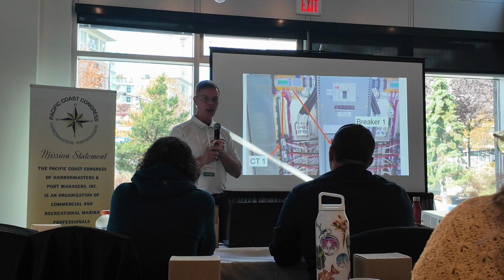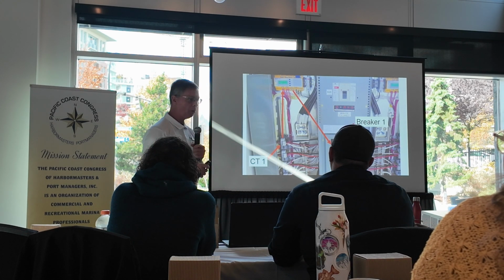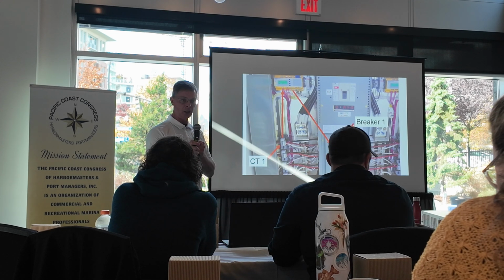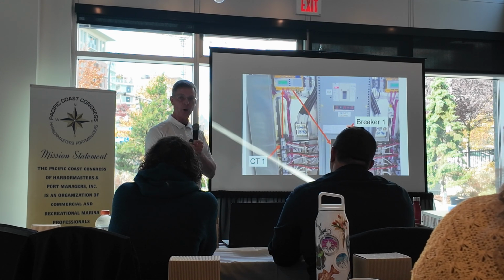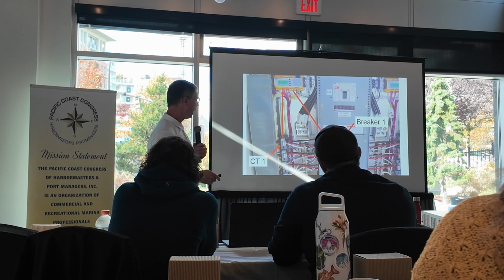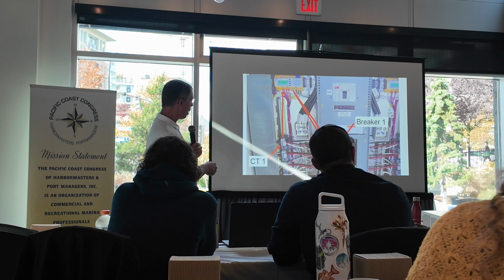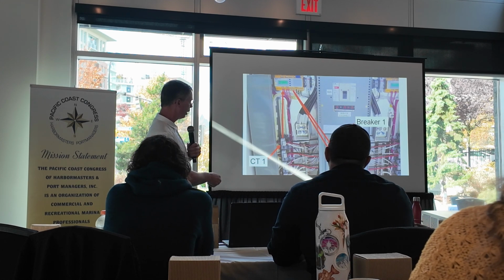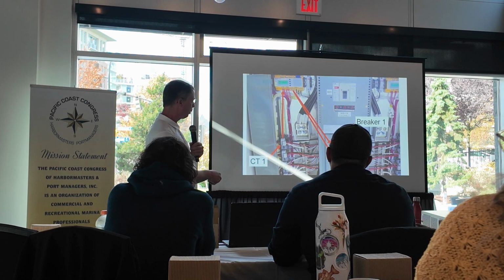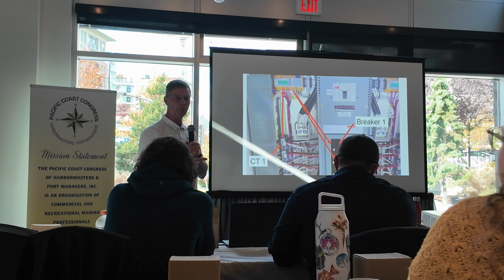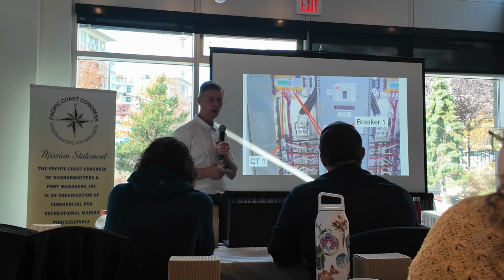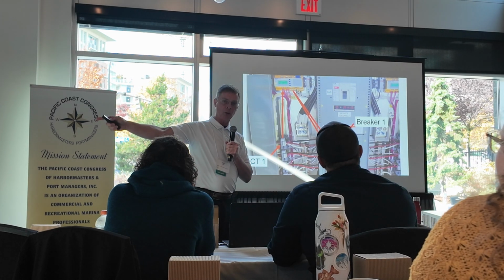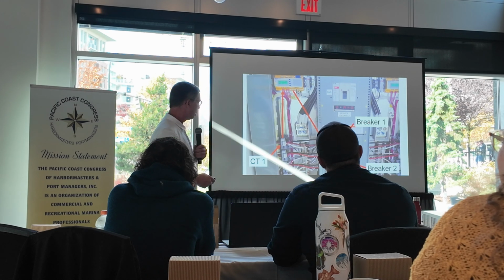Okay? When I started inducing leakage current, I would increase it at 80, 90, up to 100, 110, 120, and I heard something. I heard like it tripped, but the circuit was still energized. What happened was, instead of the wiring going to here, it actually went to breaker 2 and would trip breaker 2 instead of breaker 1, leaving my circuit energized, but tripping power on the neighbor's circuit. Okay? So what happened, it tripped breaker 2.